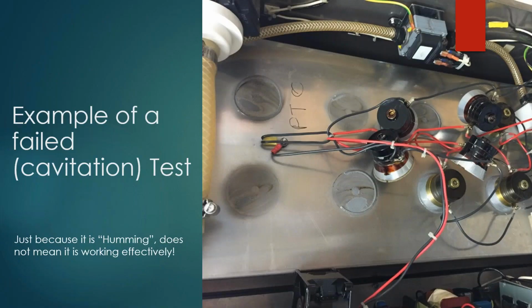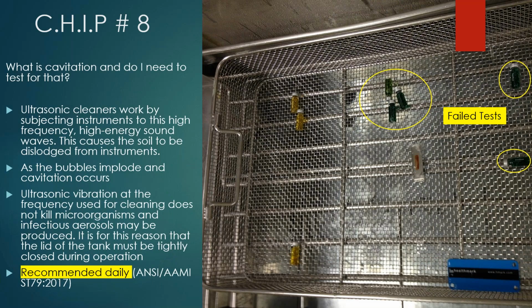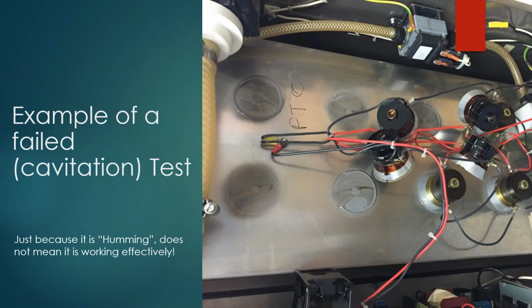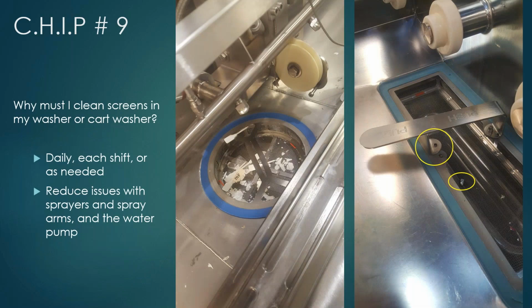And that is because of this picture. Now, it would have to be flipped over to be representative, but when you see on the right-hand side the transducers attached, that is why the tests on the left side of the previous picture have changed color. And as we go over here, with the transducers disconnected, no cavitation is being produced on that side of the machine, and those tests failed. Yet, it was making a lovely humming sound when we took this picture. So that can't be the way that we decide that something is working.